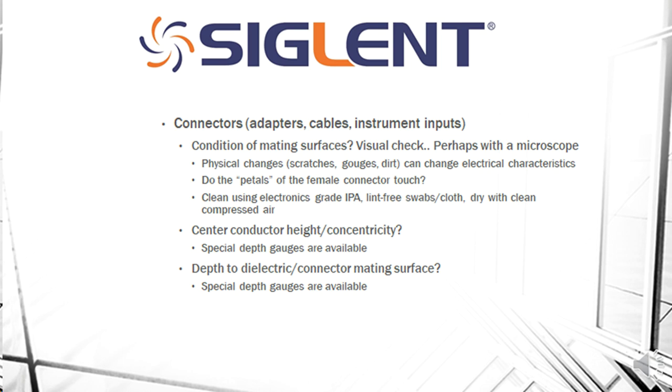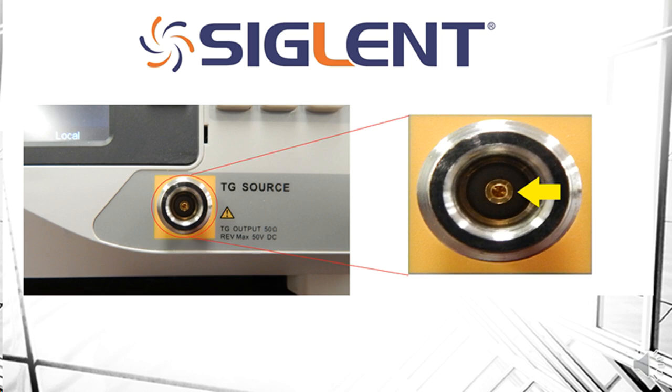We're looking for physical changes such as scratches, gouges, or dirt that can change those electrical measurement characteristics. Do the petals of the female connectors touch? Are they making good contact with the conductors?